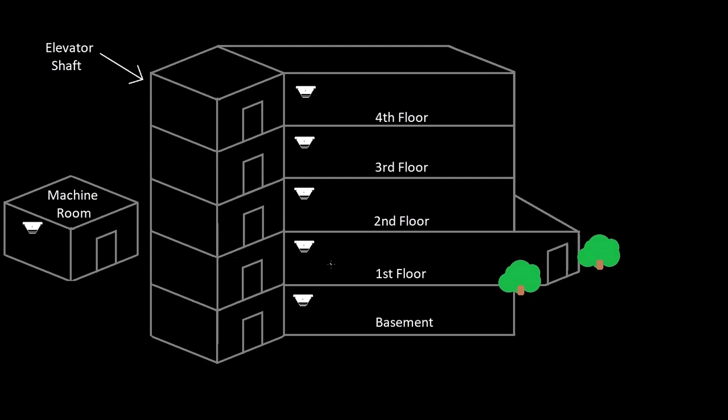You won't make that call, the elevator people will. You'll just need to have one relay representing the first group and another relay representing the other group. I threw in some addresses here and they seem a little bit random, and they are. What I ended up doing, the reason I wanted to make them random, is to stress that the device address doesn't matter - it's how you zone it or group it that matters.